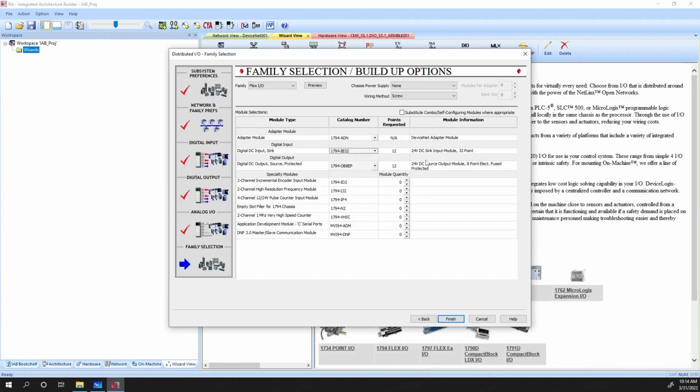And personal opinion, guys, anytime you're prepping equipment, have extra I/O. At least like 3 or 4 of each minimum. It will save you so much hassle in the long run because it's like, okay, yeah, we put this in. One of our outputs got burned out. Well, if you don't have any extra outputs, now you have to go source another card or replace your PLC completely. So you have to unwire everything and put a whole new one in, or you have to add another output module to be able to have an output that you need.